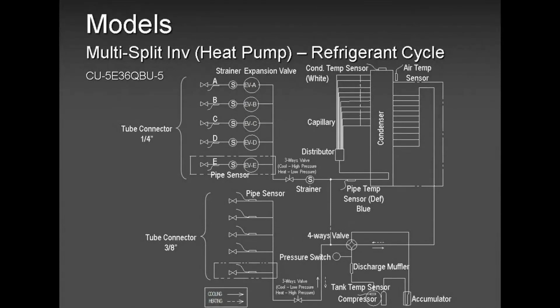So all this info is available in our service manual as well as our installation manual. It tells you when the indoor unit is below, and it also tells you when the indoor unit is up. So always keep that in mind. Because why? If there is not enough oil return because you exceeded the limitation, you are going to get a call in less than 9 months. A compressor has failed. And our compressors, normally they don't burn out. They just seize. And we have noticed, in most cases, they have seized because the contractor forgot to add the refrigerant required.